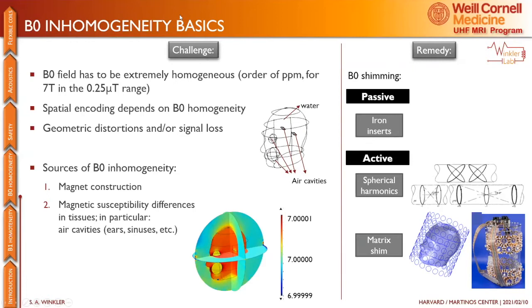So the reason why this is so important is the B0 field has to be extremely homogeneous. I think it's on the order of parts per million, on the order of 0.25 microtesla for 7T, which is a pretty large dynamic range, which always requires a lot of engineering finesse. And spatial encoding depends on this homogeneity. So if you don't do this right, your image will show anatomies in a different place as compared to where they are in reality. And of course, there's also signal loss related to it.